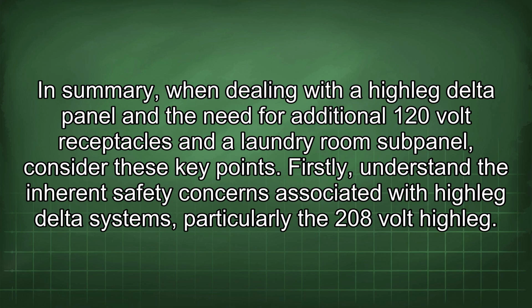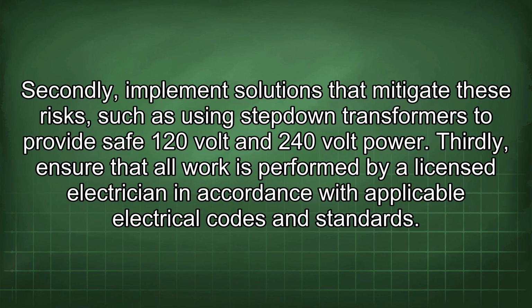In summary, when dealing with a Highleg delta panel and the need for additional 120-volt receptacles in the laundry room subpanel, consider these key points. Firstly, understand the inherent safety concerns associated with Highleg delta systems, particularly the 208-volt Highleg. Secondly, implement solutions that mitigate these risks, such as using step-down transformers to provide safe 120-volt and 240-volt power. Thirdly, ensure that all work is performed by a licensed electrician in accordance with applicable electrical codes and standards.